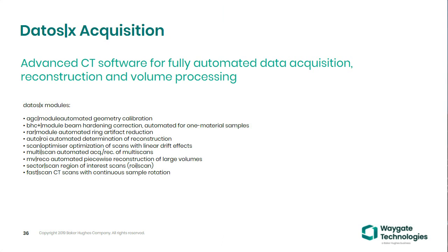On the Datos acquisition side, this is our standard acquisition software on all of our CT systems. It allows for scripting and automated data acquisition. It's got all of our typical features: multi-scan, beam hardening corrections, scan optimizer, etc. You can utilize all the same features that you use today in your conventional systems on this system as well.